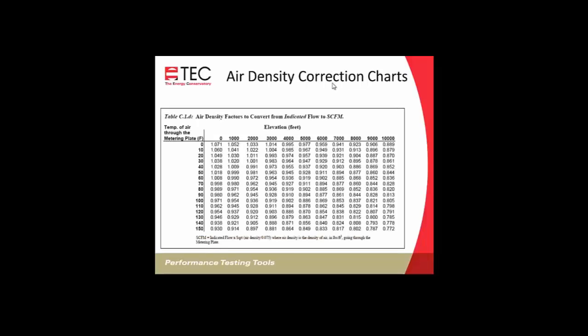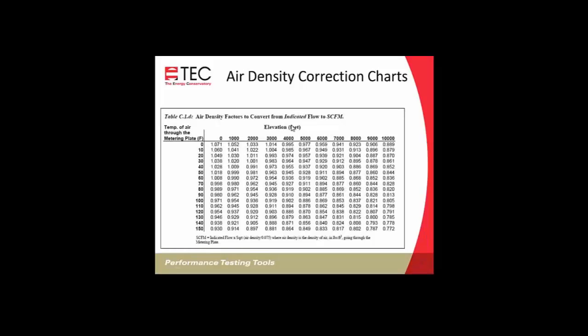Sometimes you'll be comparing with standard CFM, SCFM, which is converting your flow to what it would be if you were at sea level and 68 degrees. So if that's the method you're using, then if you're at 7,000 feet and 70 degrees, you'll need to multiply your number by 0.877 from the indicated flow. And indicated flow is the flow being read on the gauge. So the flow that's being read on the gauge, you'll need to multiply it by 0.877 to get it back to sea level. Then you can use that 400 CFM per ton, for example.